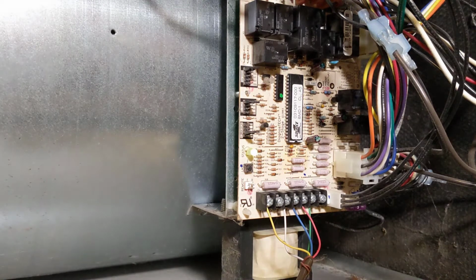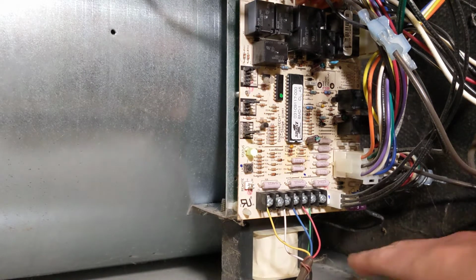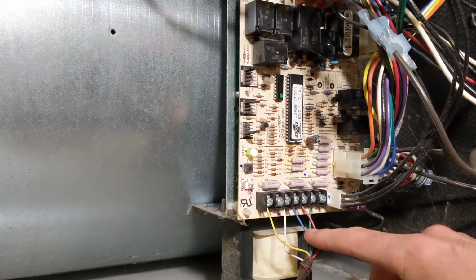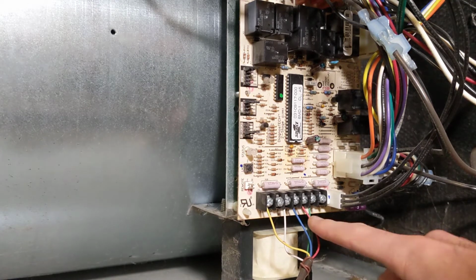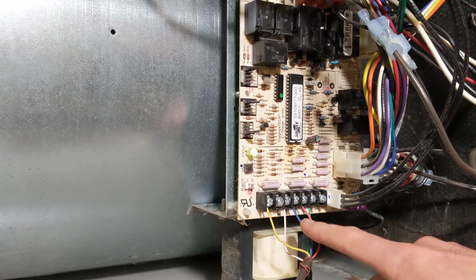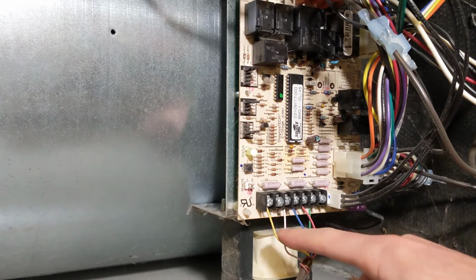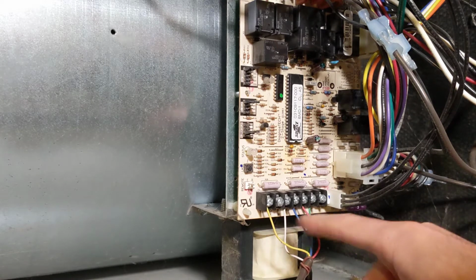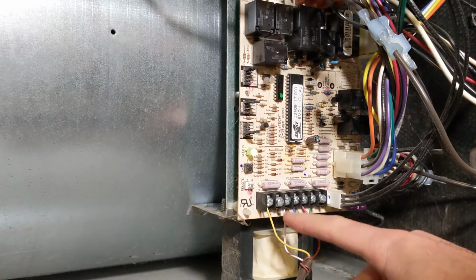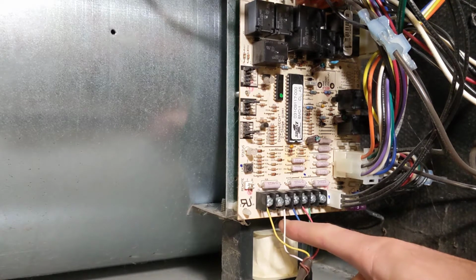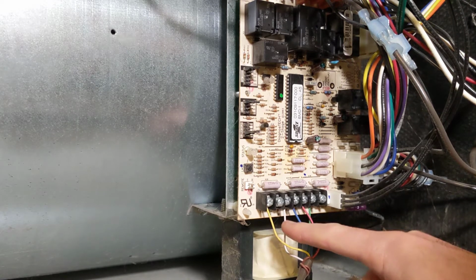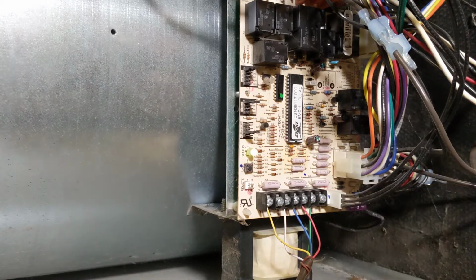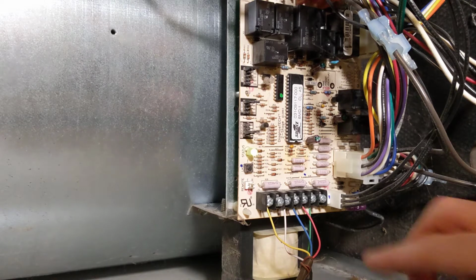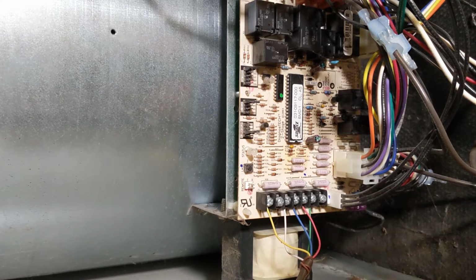There's kind of standards to what wires you should have. There's a green wire that's ground, and that's kind of a standard industry thing. We have a red wire that's going into R, so that makes sense. And then typically you'll have various other colored wires, but the one for heat is typically white, and it goes on the W terminal. So this is white, and then we have our red. Now what the thermostat does is when it calls for heat, it basically just connects red and white together. And that's what switches on heat.